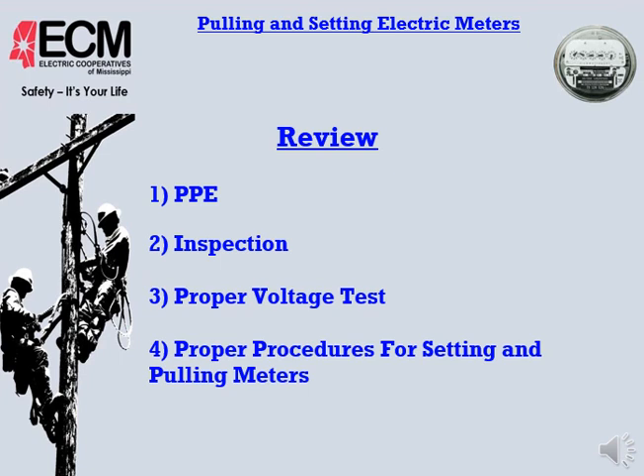Number two: has our inspection process been done completely? Whether pulling or setting a meter, we still need to inspect from the road all the way to the meter base. Has our voltage check been done correctly? We've taken all the steps we talked about to check voltage and taken all necessary precautions before setting any meters. And we need to make sure we're using proper procedures whether pulling or setting meters - those steps are very similar, so let's make sure we use the procedures we talked about.